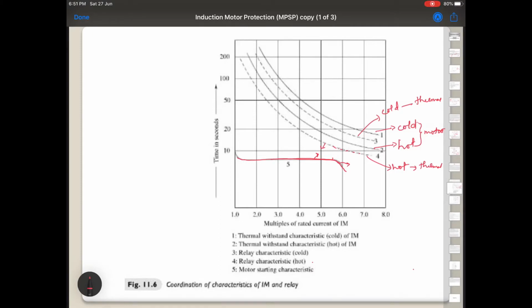So because of that, you choose a hot characteristic of the thermal relay a bit above that, which also leads to unhealthy starting. So to avoid this, we are not using a thermal relay here. To avoid early tripping of the thermal relay because of a high inertia load, a microprocessor or DSP based relay is the best relay that could be used for an induction motor during starting in hot condition.